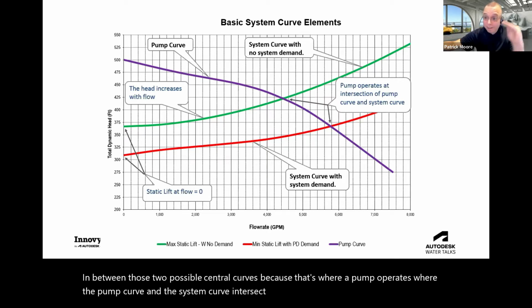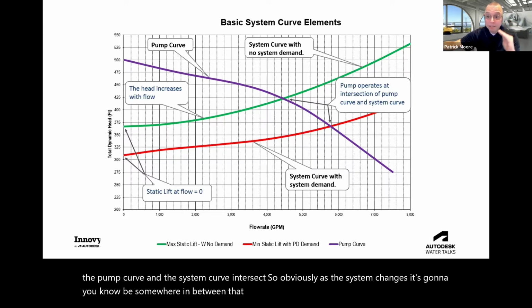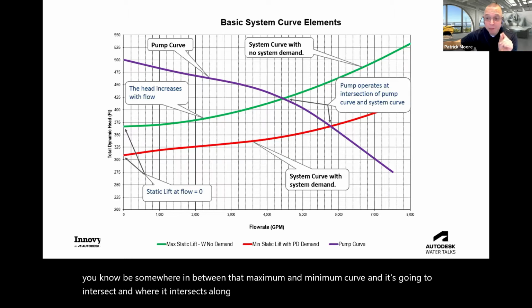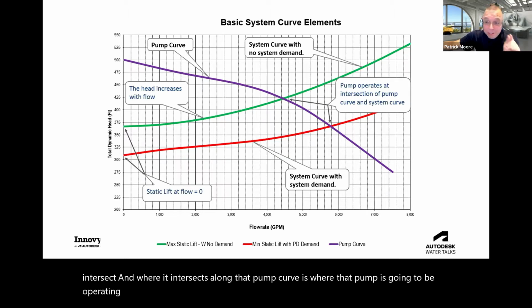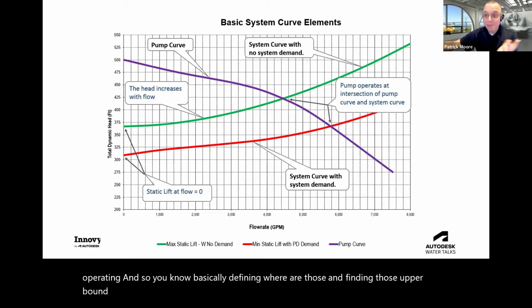So obviously, as the system changes, it's going to be somewhere in between that maximum and minimum curve, and it's going to intersect. And where it intersects along that pump curve is where that pump is going to be operating. And so, basically defining those upper bound and lower bound curves is going to be the magic, right? That's the important part.